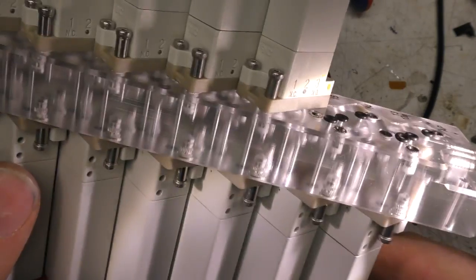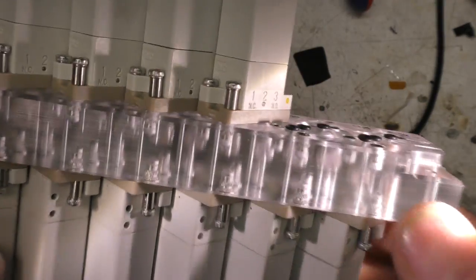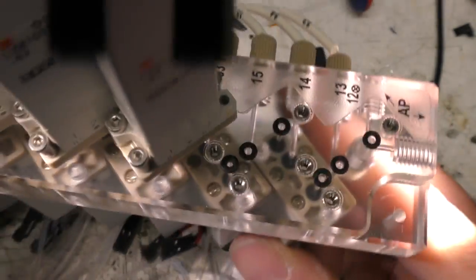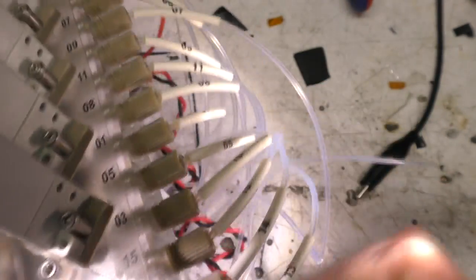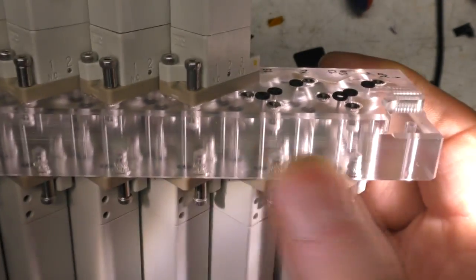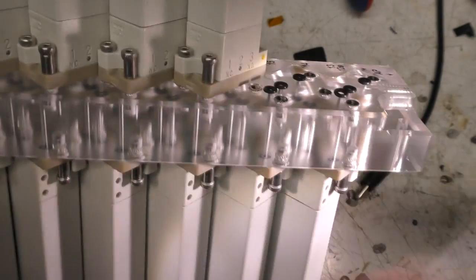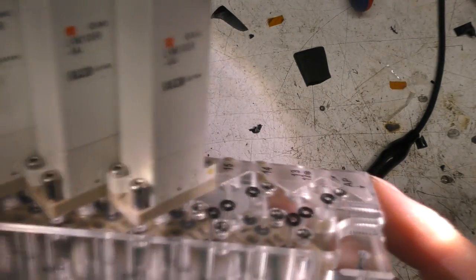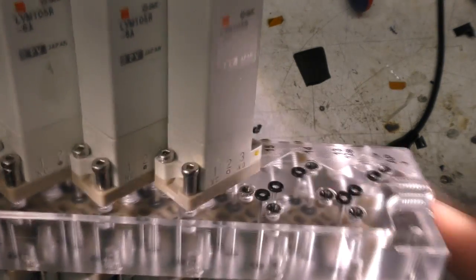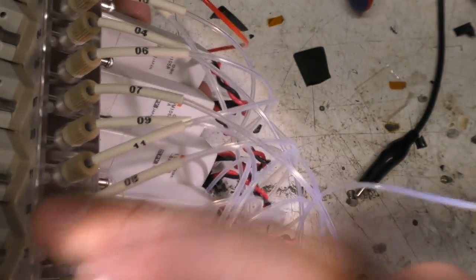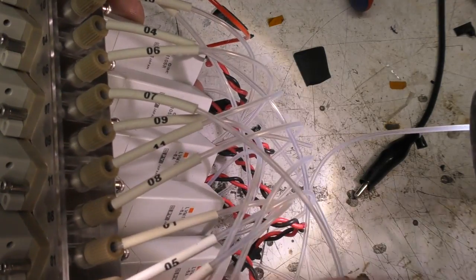So this is the valve and manifold assembly. This is basically a block of acrylic. It's got various holes drilled to allow fluid. So it looks like we've got a bunch of connections here, and it's a bit hard to see because this side isn't particularly well polished, but it looks like there's a continuous chain. Each of these valves is like a changeover type thing. So there's either a straight path all the way through, or it switches one of these into that path, presumably to suck up whichever reagent it wants to, and then there's probably an alternate one where it can suck up the cleaning solution.